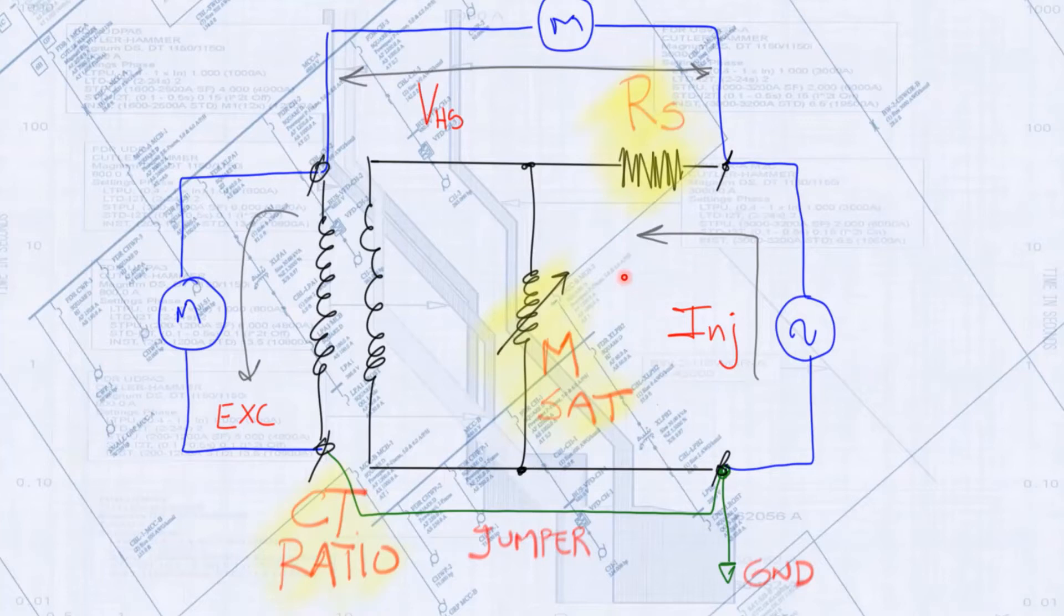The main purpose of testing the CT is to evaluate its performance for the intended application. The main three characteristics that help us evaluate and apply CT calculations are the ratio, the saturation curve, and the secondary winding impedance. The standard method for CT testing generally consists of injecting current through the secondary terminals of the CT and measuring excitation on the primary side of it, and between the H1 and X1 terminals.